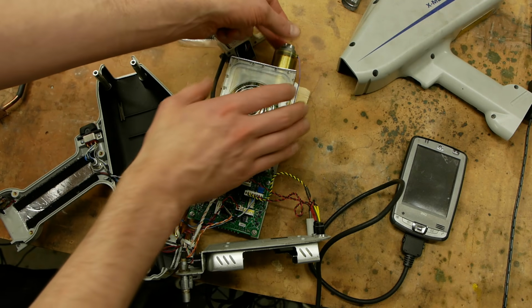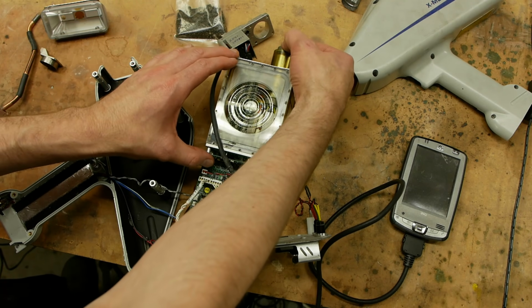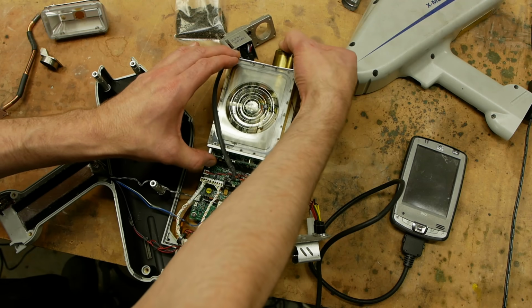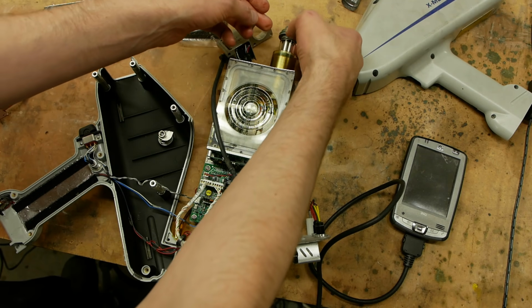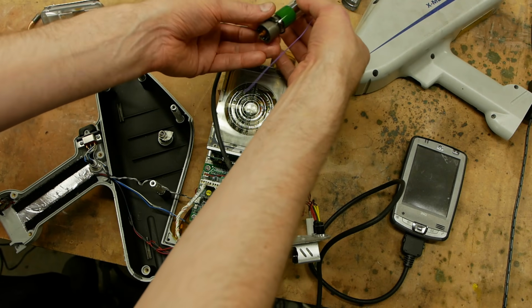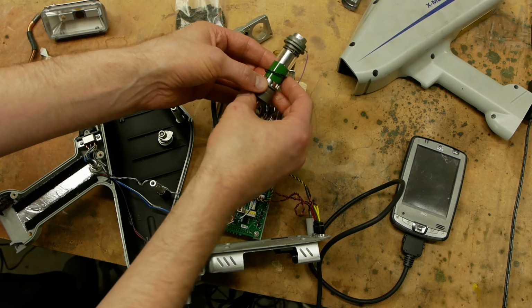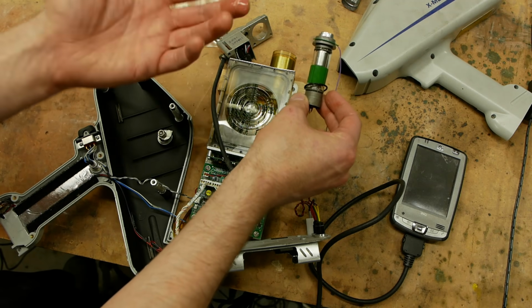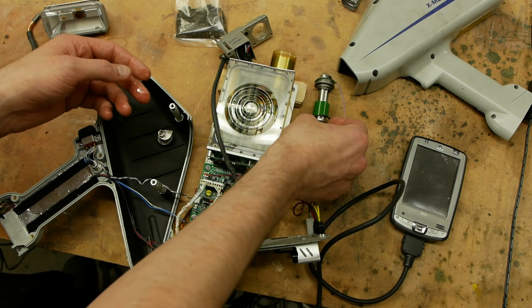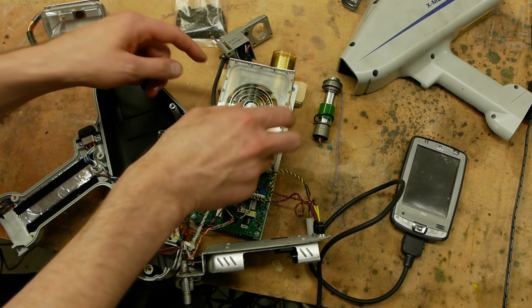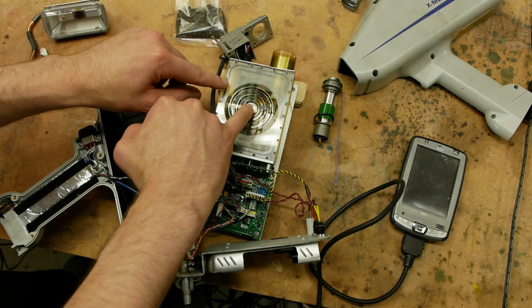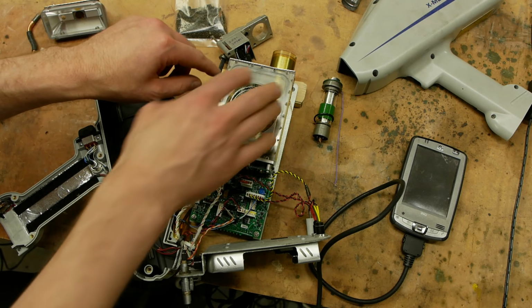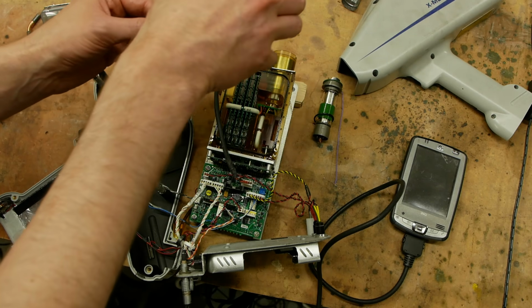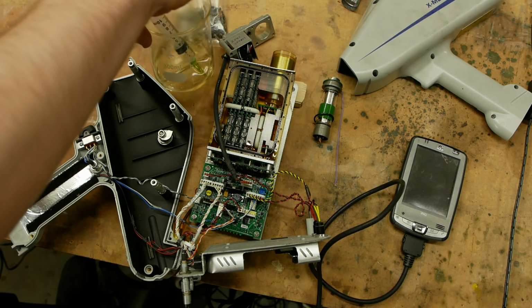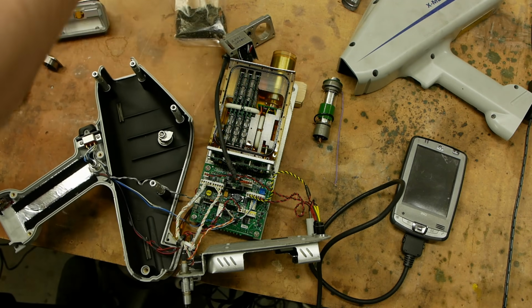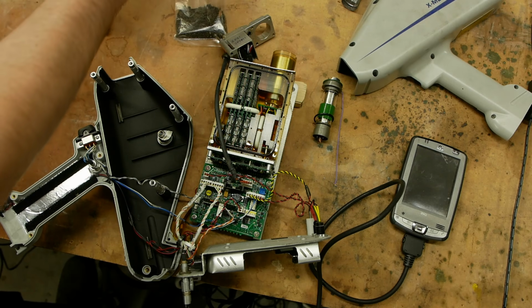And then on the other side, this is the X-ray tube, and it also just unplugs, if I can get a handle on it here. And there we are. So the X-ray tube is a traditional construction thing. I should point out that this pack here, actually, let's open it up. It has this very funny expansion bellows here because this whole chamber was filled with oil. And so I had to use a syringe and suck out all that oil, which is messy and gets everywhere.